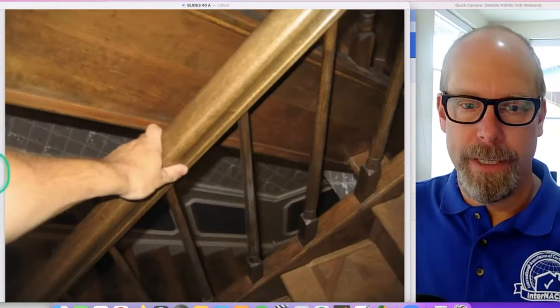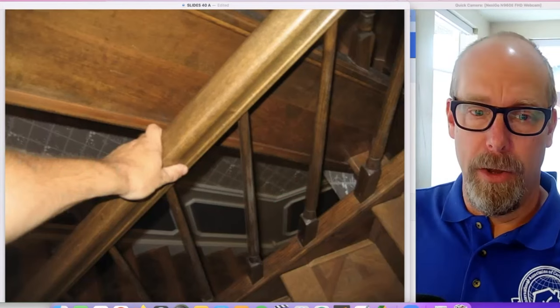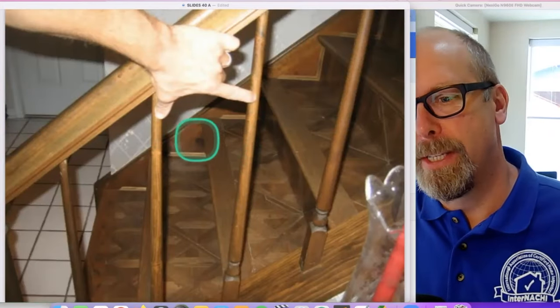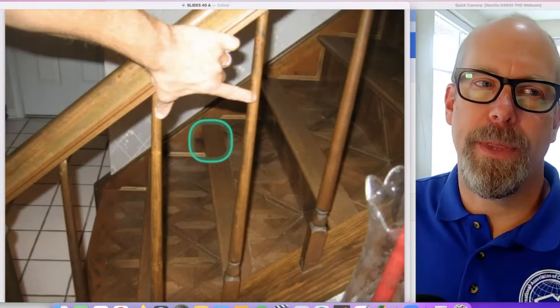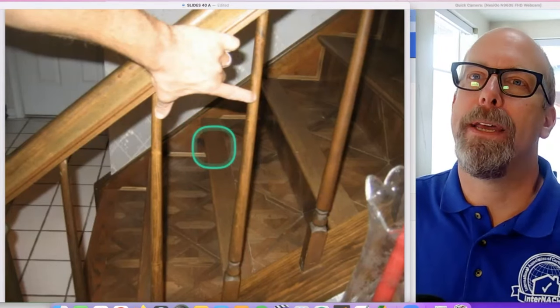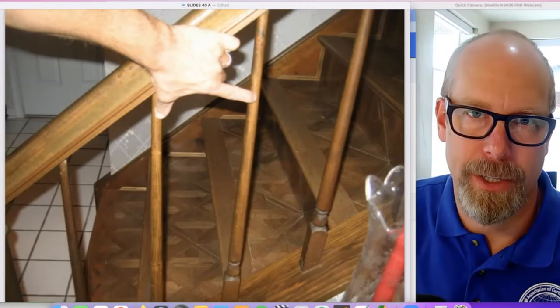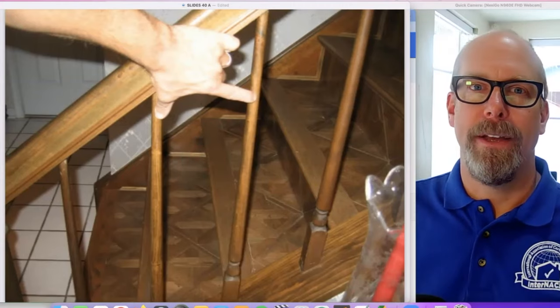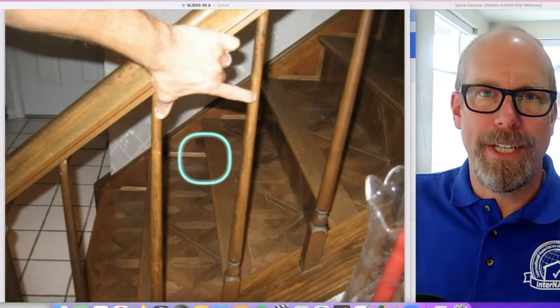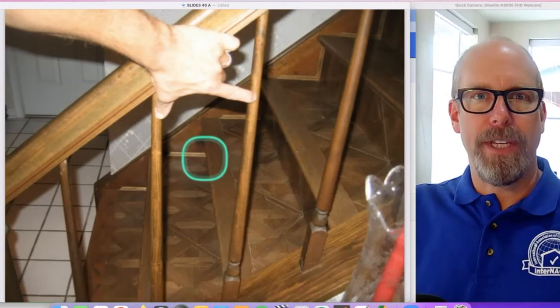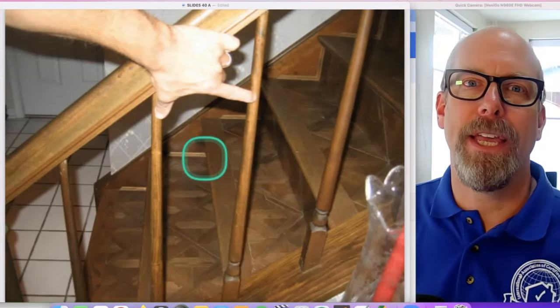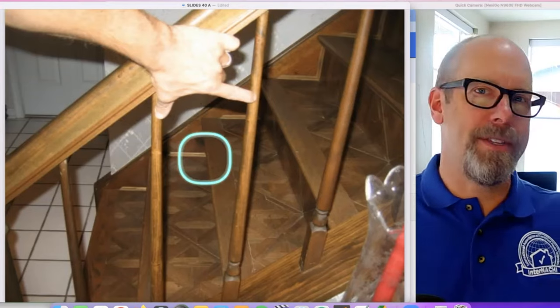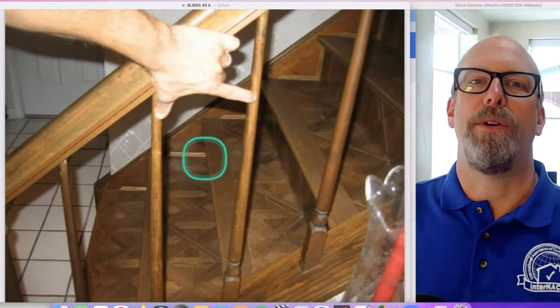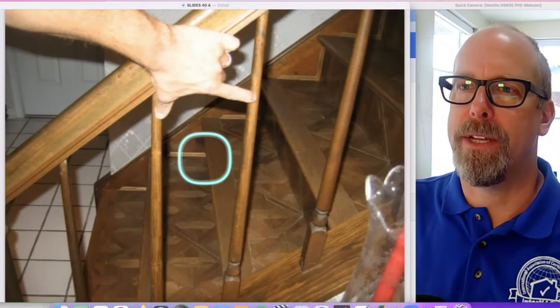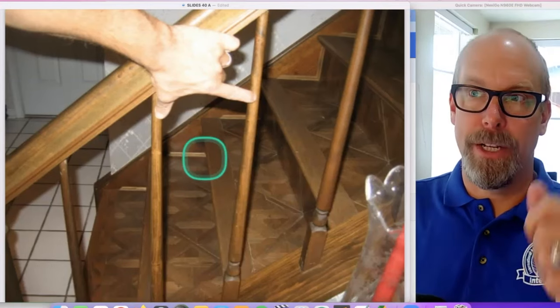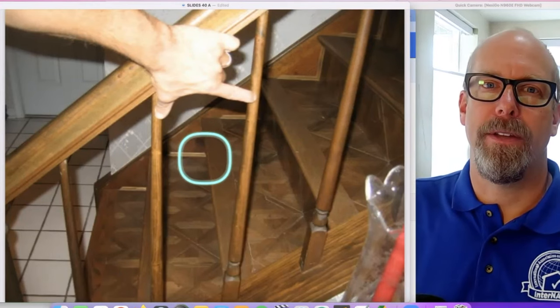Got a railing, same thing, space between the spindles too far apart. It was built to code, I don't care, it's just not safe anymore. It's like bedrooms without AFCIs, that's the modern standard. It's like a garage without any GFCI protection. It's like kitchen counters, the code has changed. It used to be that only within 6 feet from the sink needed GFCI protection. Now it's everything, every counter, doesn't matter if it's across the room without a sink. All kitchen counter receptacles should be GFCI protected.